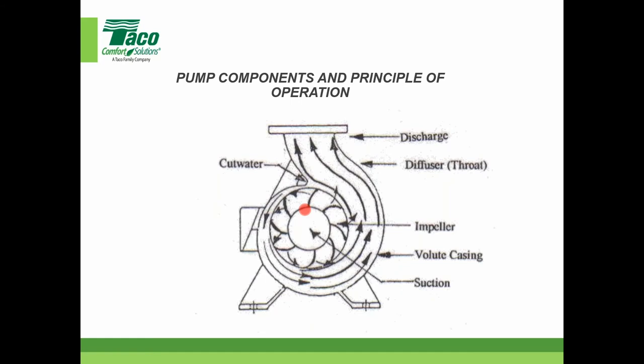I wouldn't be surprised for the most part. Each pump size is a little different. And for the most part, the impellers are bronze material. There are some stainless ones there, but for the most part, they still are probably bronze. The other thing that we do, and I wouldn't be surprised if others do it as well, we balance every one of our impellers. We have a pretty slick machine that spins it and takes some readings and sees where we have to take some weight off. So instead of like a tire where you add weight to balance it, we actually grind off some weight, or the machine does, to balance our impellers.